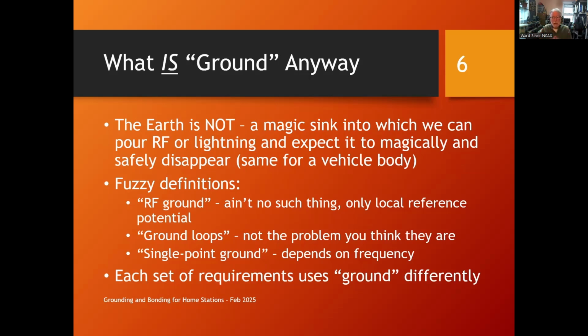I understand that, and so they don't like ground loops, and they will break ground loops specifically to prevent that from happening. Also, audio guys don't like ground loops because if you have a loop and there's a magnetic field going through that loop and that magnetic field is changing, that loop will pick up voltage proportional to the area of the loop, and it will cause a current to flow in the loop.